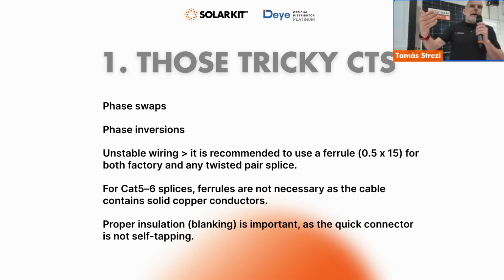You have to provide a stable load to the house and check your values. You have to read positive values when loading up the phases individually. You can even do this on the inverter terminals with probes and the load. You should immediately see a positive value. So you load up L1, you read a positive, increasing value in CT1, you are good. And then you go in turn, and that's the basic method. It's especially important when you have to extend the CTs. If you are using Cat 6e, which is 20 meters away, you might miss the actual pairs of wires. But with this loading method, you can pretty much blindly find out the right pairs and the right direction of the CTs.